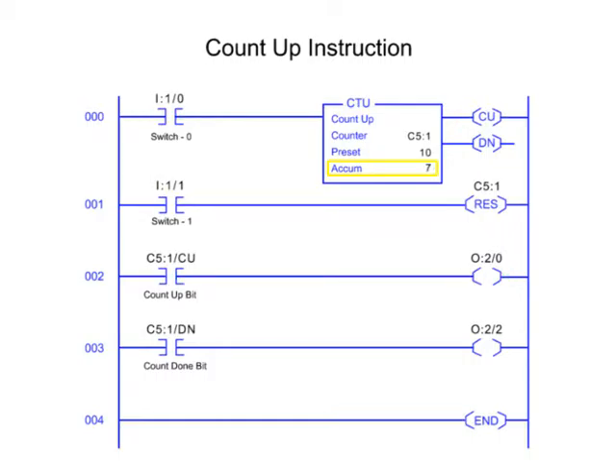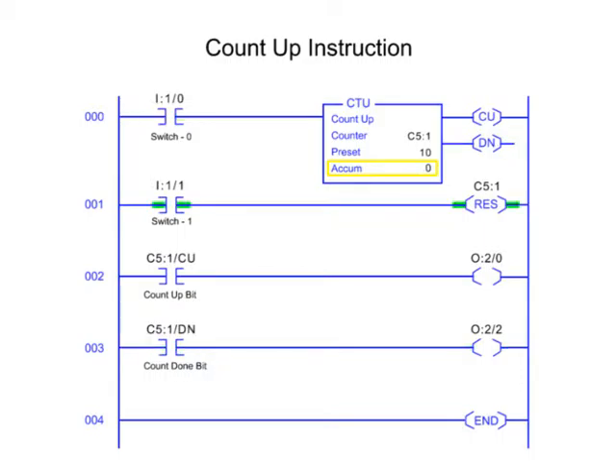After the accumulated value reaches the preset value, the counter instruction Done Control bit is enabled. The accumulated count is retained until cleared by the Reset instruction addressed the same as the counter file.